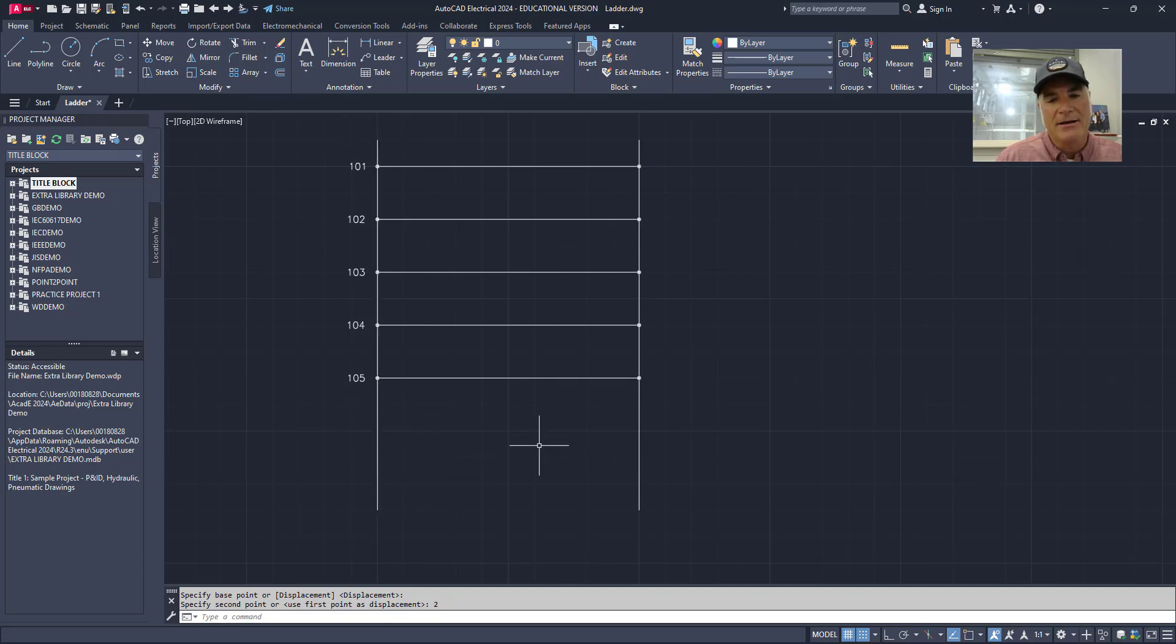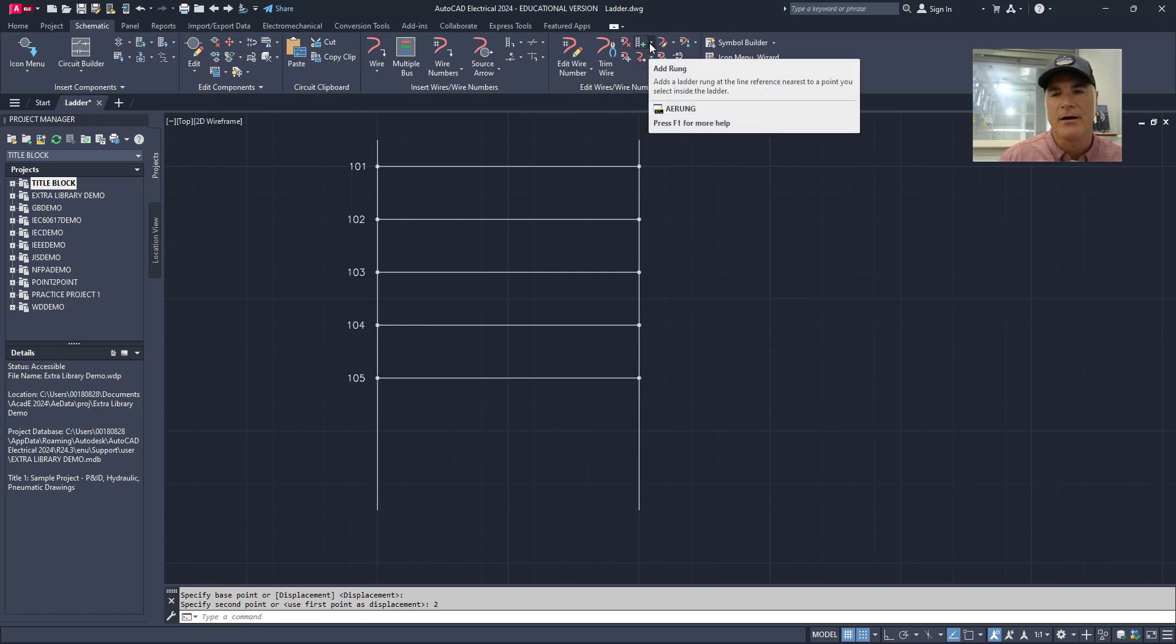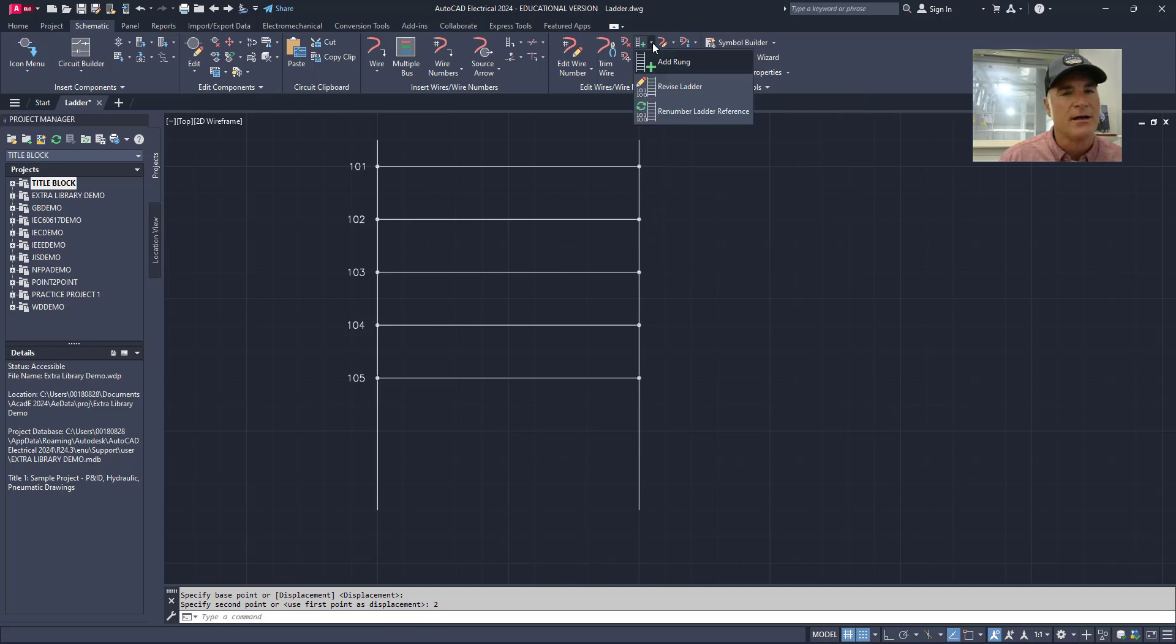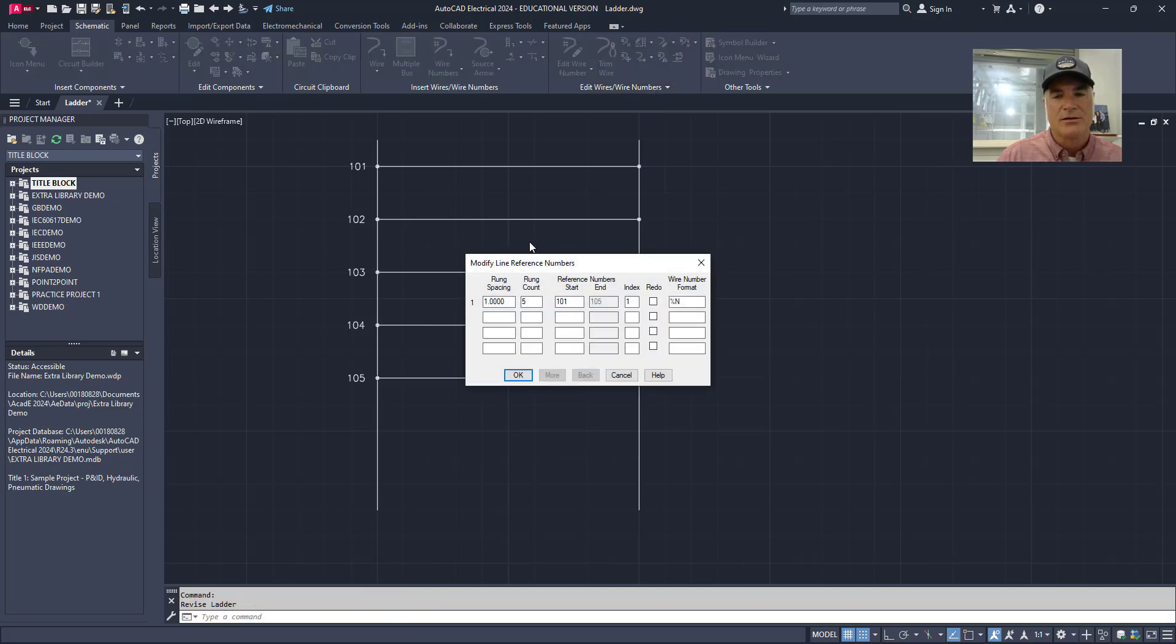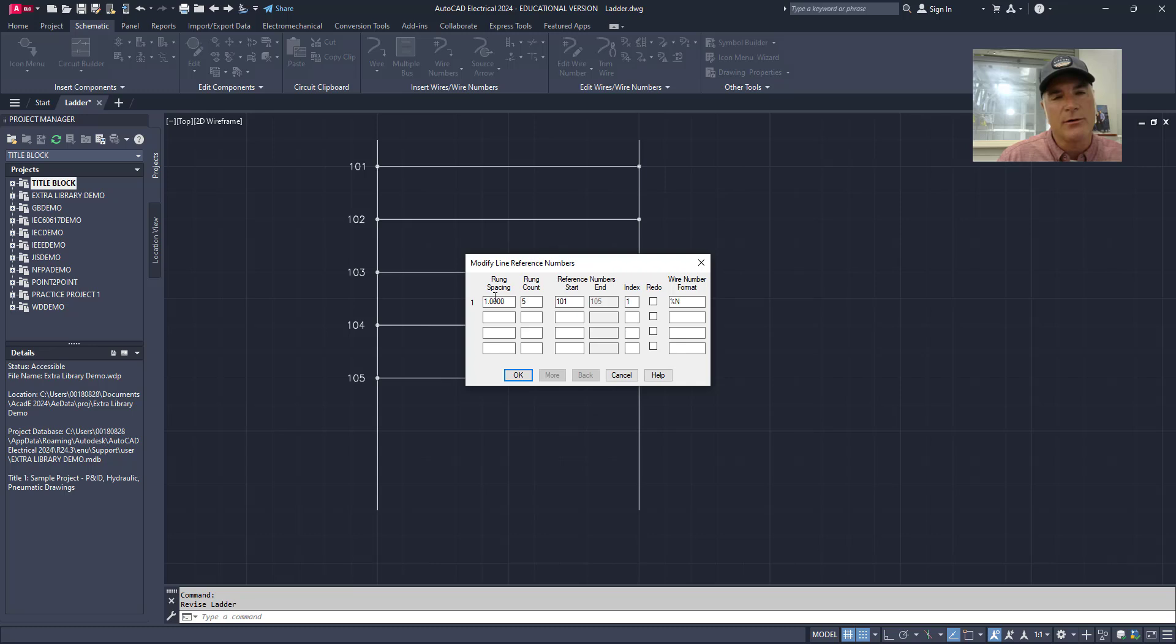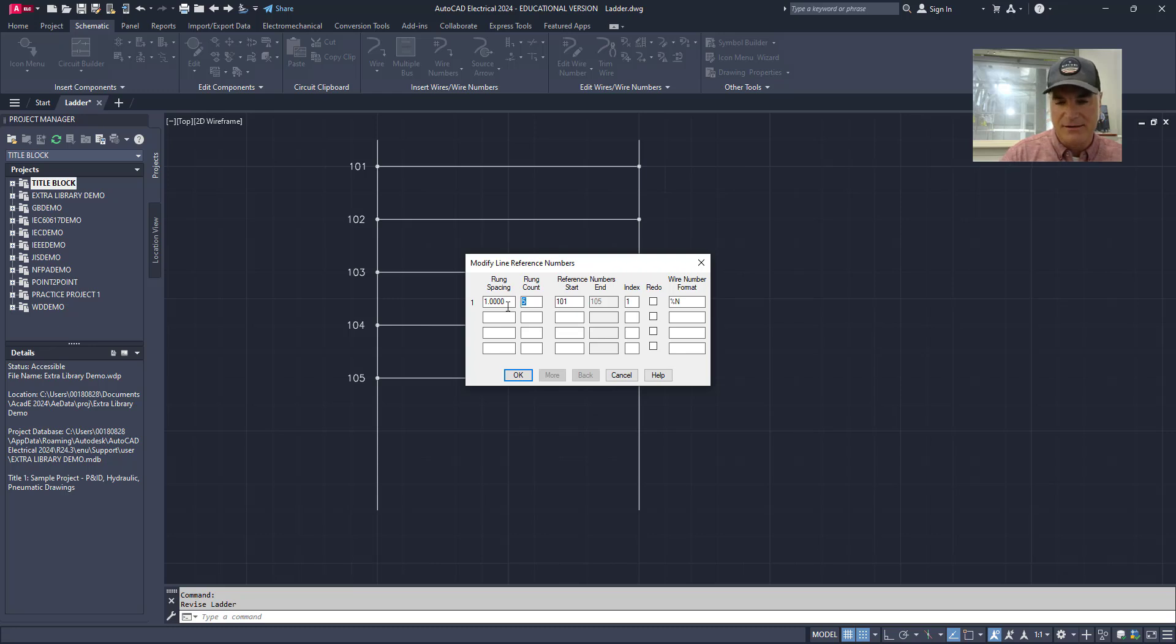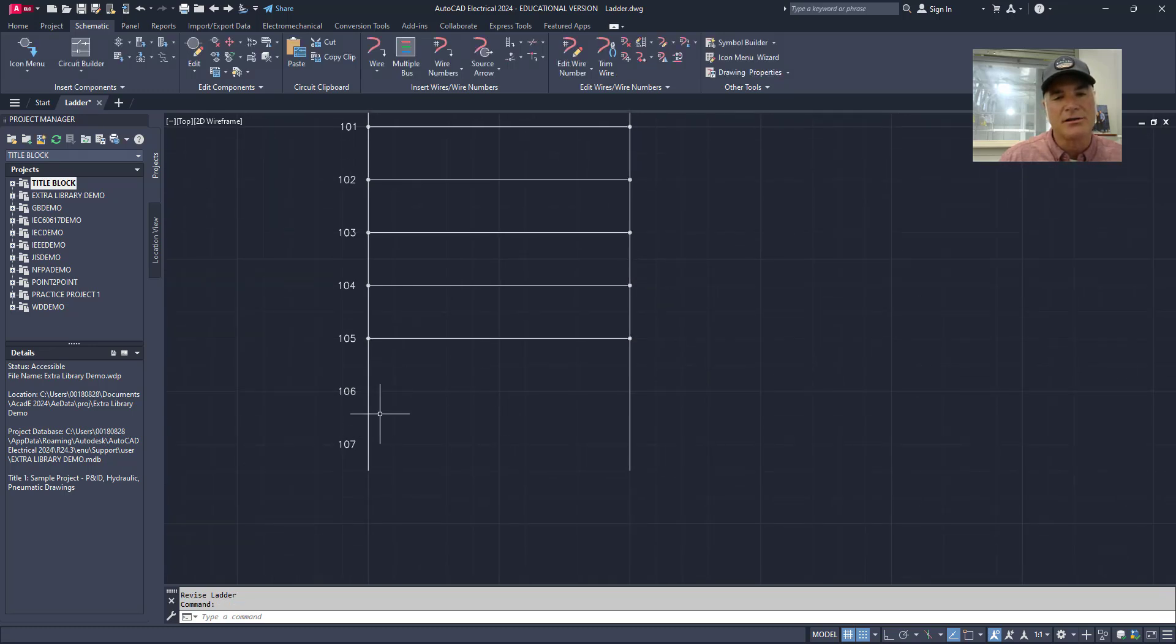Now in order to add two more rungs to this ladder, what you have to do is go back to the schematic tab and you're going to go to the edit wires and wire numbers panel. And then right here where there's an add rung, if you look at the little flyout, there's other tools here and we want to revise this ladder. So when I click revise ladder, it will open up or give me the information about any ladders in this active drawing. Right now I only have one ladder in this drawing. The rung spacing is one, the rung count is five, the rung start is 101. And I can change any one of these numbers that I want or all of these numbers if I want. For example, I know that I want this to have seven rungs. So I'll just type seven there and choose OK. And you'll see that it adds two rungs to this ladder.